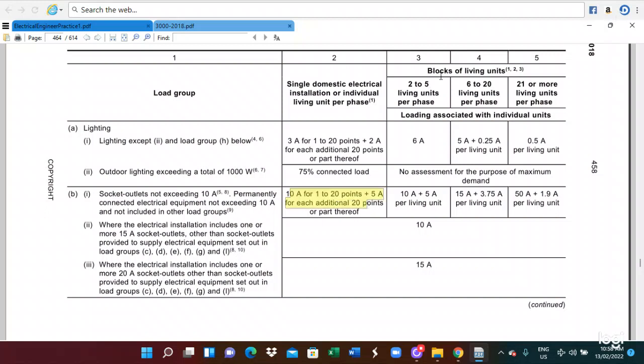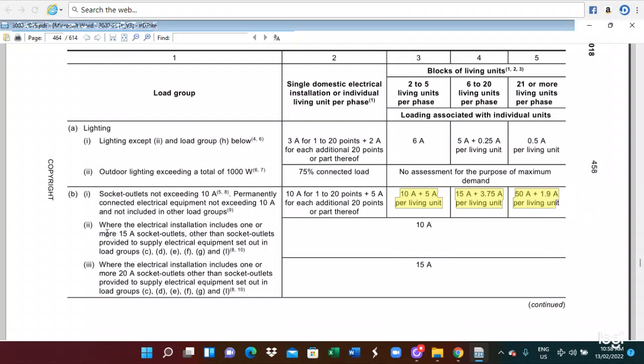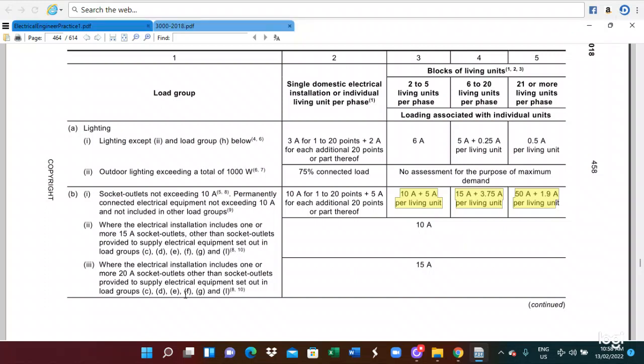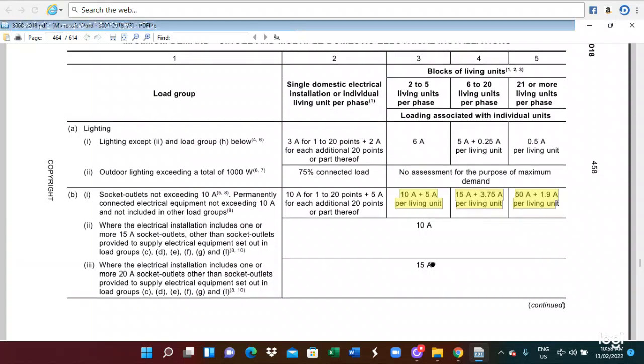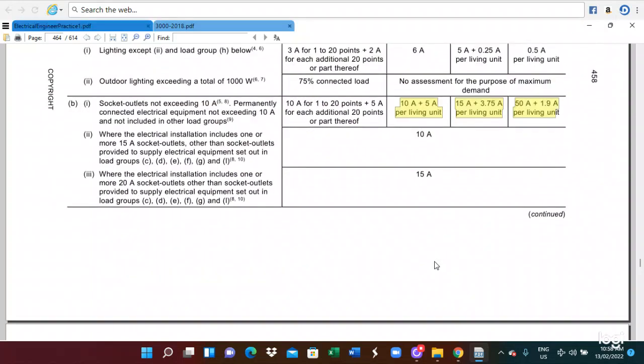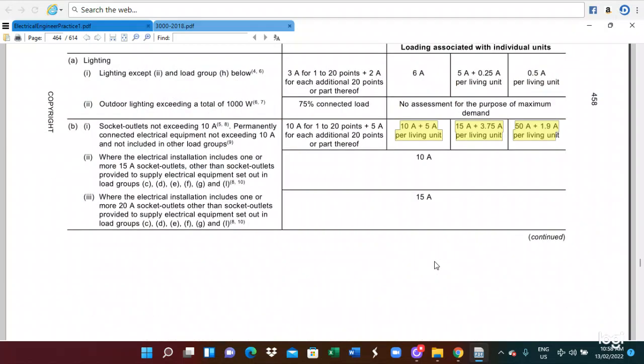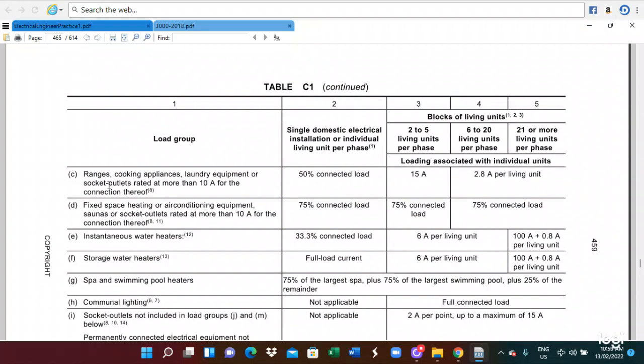For block living, you refer to this rule. For socket outlets not exceeding 10 ampere, you just take 10 ampere. In an electrical installation with more than a 20 ampere socket outlet, you can take 15 ampere. This depends on the load group. Depending on the load group, you can select the appropriate maximum demand current. In the meantime, if you install a range or fixed space heating, an instantaneous water heater or a storage water heater, those are the load groups. So Table C1 is for the domestic installation load group.